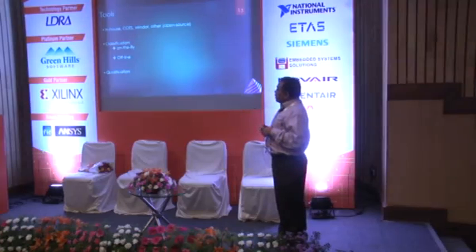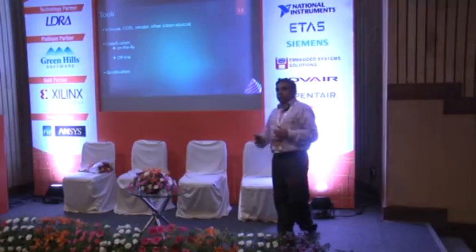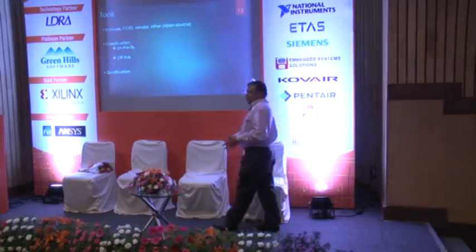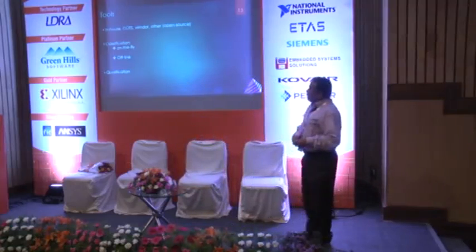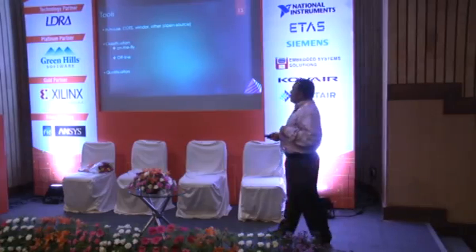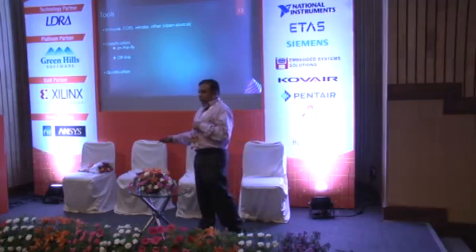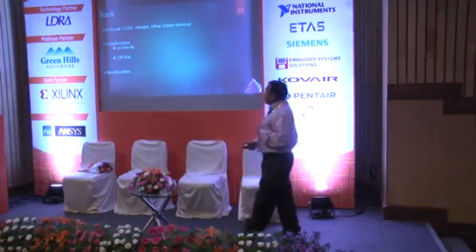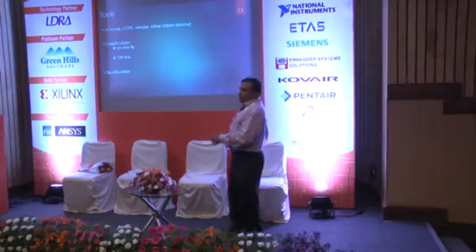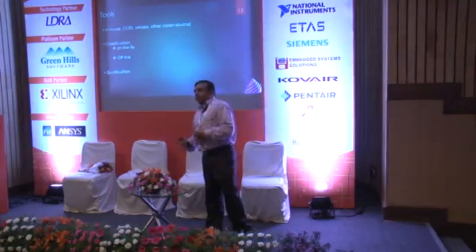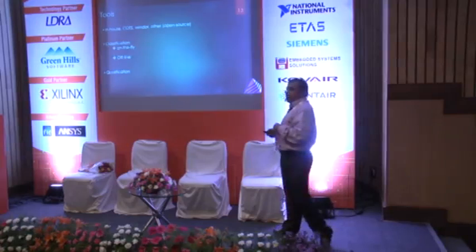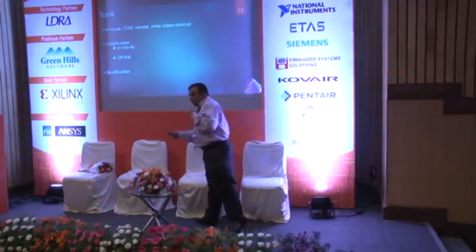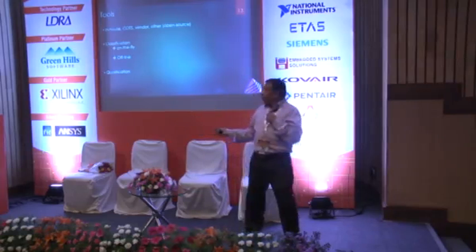So, usually the tools can come from in-house, which means we have developed our own tools, maybe as part of this project itself, or maybe some other department within the organization. It could be COTS, or we have asked a vendor to develop a tool for us to be used in this particular project, or it could be any other tool coming from open source. So, the moment that tool has an application in my activity, first thing is they have to be classified. So the 61508 gives two types of classification, online, also called on the fly, or offline.